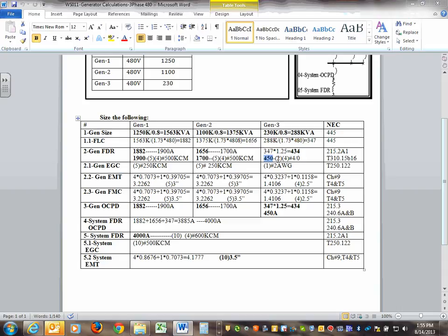And they are not 100% assembly, but I threw one baby one, 230, and the other ones are the bigger ones with 100% rated assembly, where you size directly to the load. You could specify 100% fully rated. If you specify a fully rated circuit breaker, rated in an assembly, then you can go directly based on the load right here.